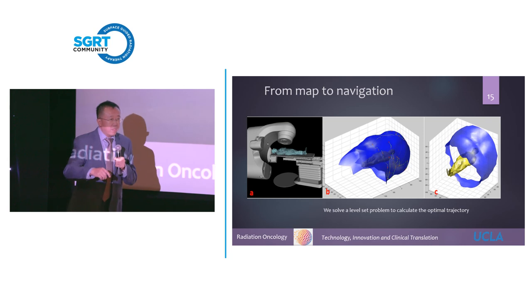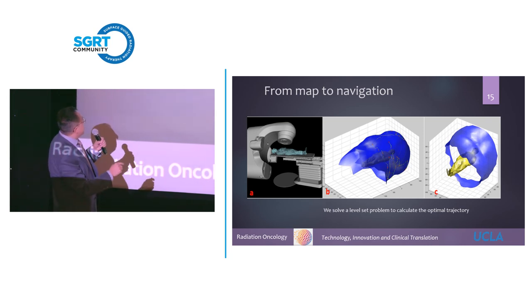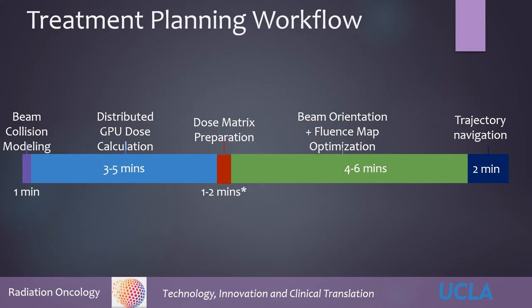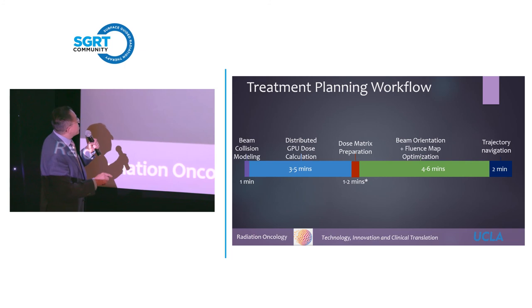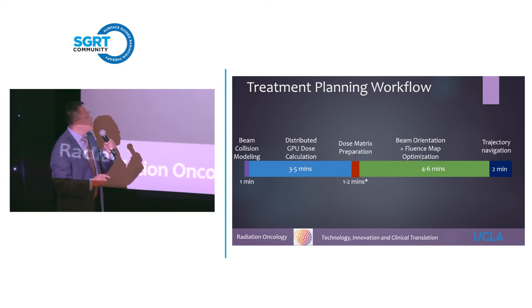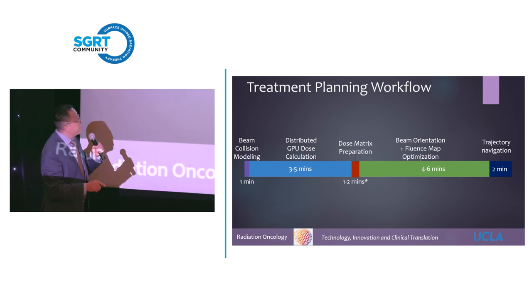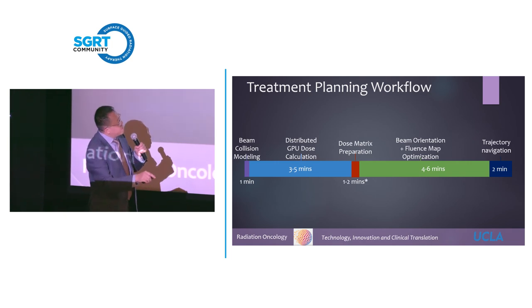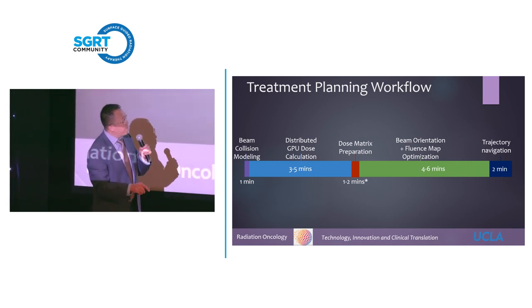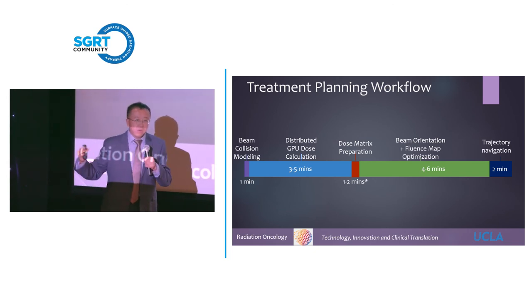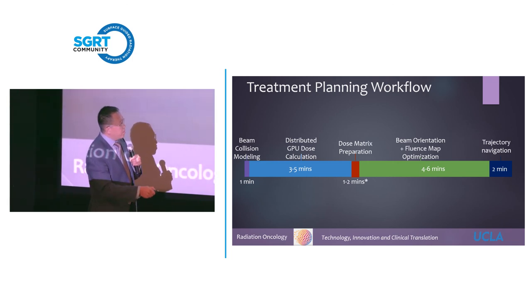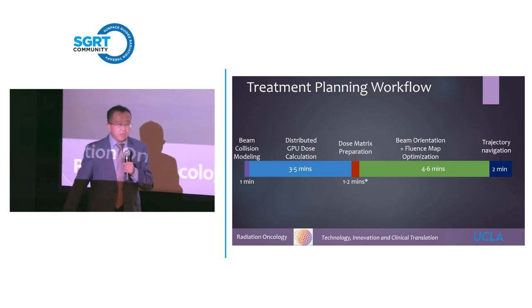This is what I envision for the future of SGRT-guided 4Pi treatment. We start with beam collision modeling, which takes about one minute. A distributed GPU dose calculation engine calculates the beamlet dose of all beams in three to five minutes, depending on tumor size. Then we prepare the dose matrix, perform beam orientation and fluence map optimization in four to six minutes, arriving at the beautiful dose distributions. Finally, we calculate the trajectory in about two minutes — a complete workflow of 10 to 15 minutes.